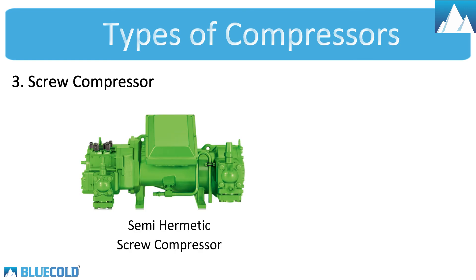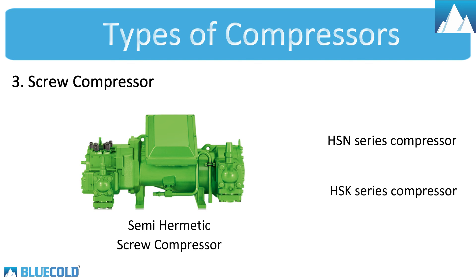Semi-hermetic Screw Compressors — these are for high-capacity cold rooms, cold storage, blast freezers, blast chillers, and industrial chiller systems. There are two types: HSN Series, for negative temperature usually below minus 20 degrees Celsius; and HSK Series, for positive temperature usually above 0 degrees Celsius.